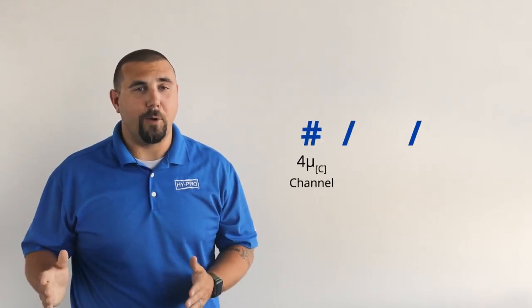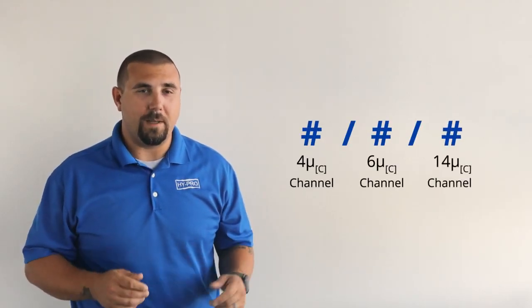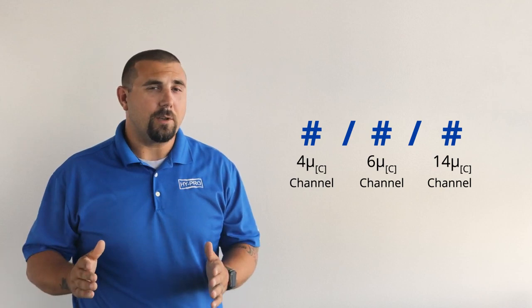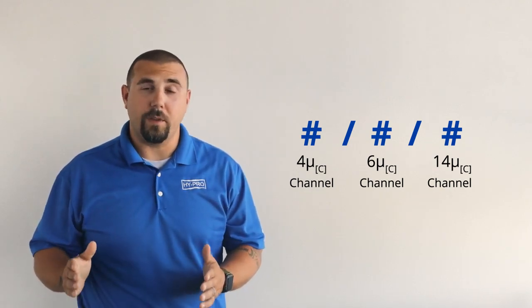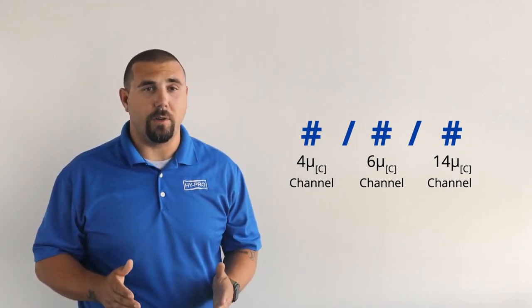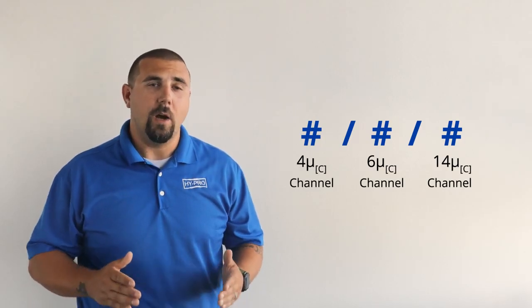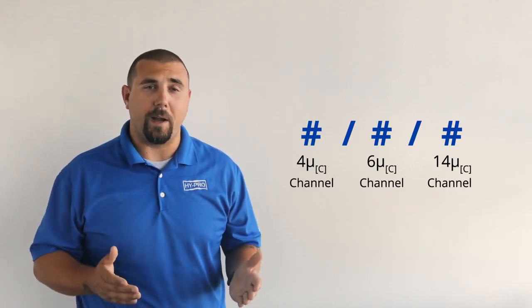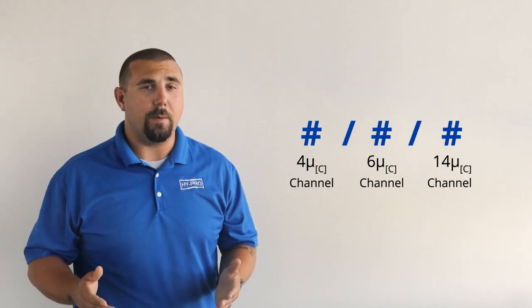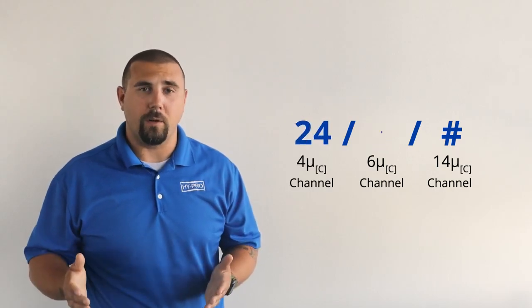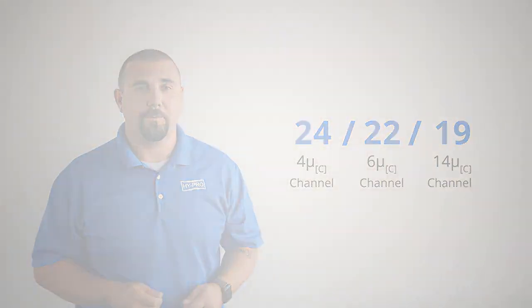ISO cleanliness codes are used to quantify the amount of particulate contamination that is present per milliliter of fluid and is measured and documented in 3 different micron sizes. Those micron sizes are 4 micron, 6 micron, and 14 micron. ISO cleanliness codes are always expressed as 3 numbers, with each number referencing a contamination code for each correlated particle size while encompassing all particles at that micron size or larger. An example of an ISO code would be 24, 22, and 19.